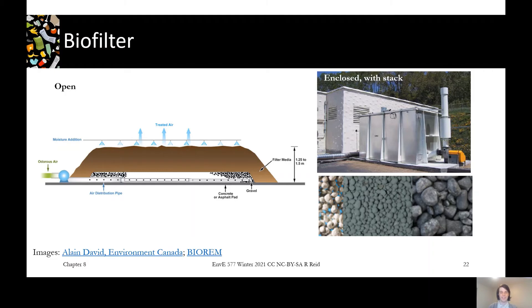So how the biofilter works is you have some media that your microbes are going to be living on and then they have water sprayed over them to keep your microbes happy as well as to help dissolve some of those odour compounds. And as you're passing air through the biofilter, it's going to dry it out. So that's why you need to be continually supplying water to make sure everything is nice and moist, your microbes are happy and you have water available to dissolve your odour compounds. So similar to the packed bed wet scrubber, the biofilter is going to provide a high surface area between these wet media particles and the process air coming through.